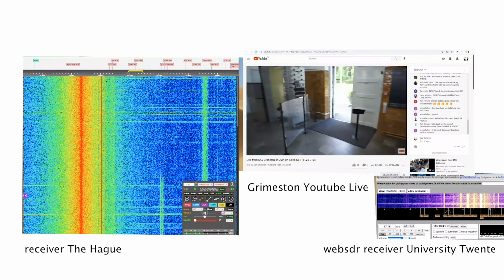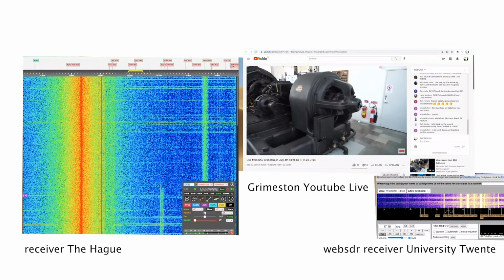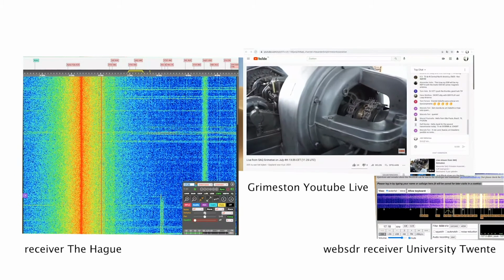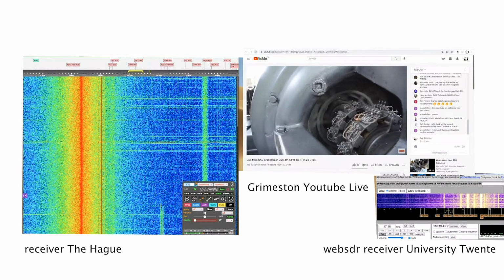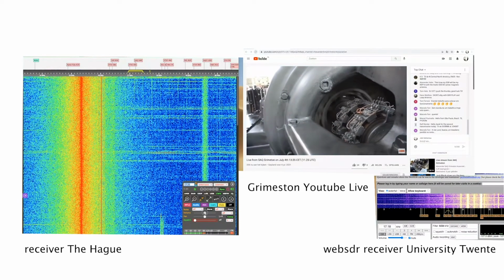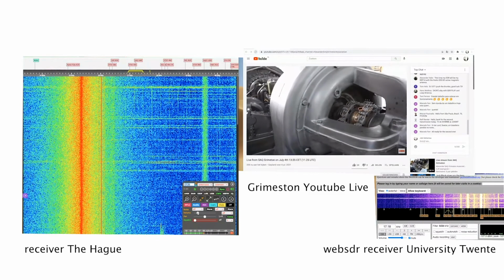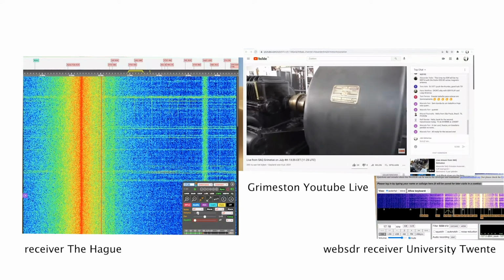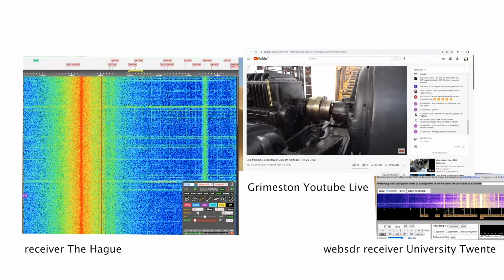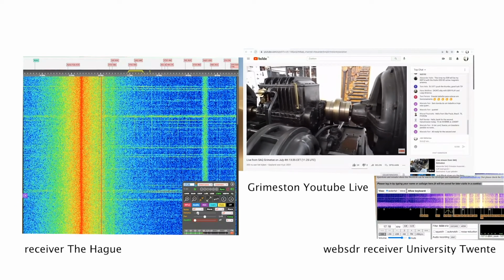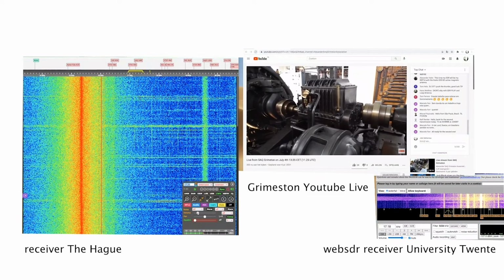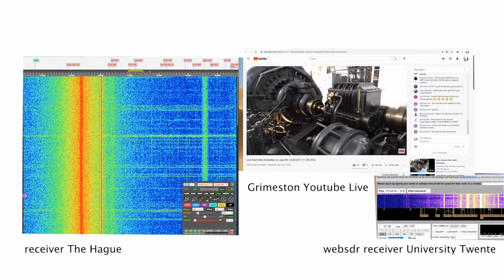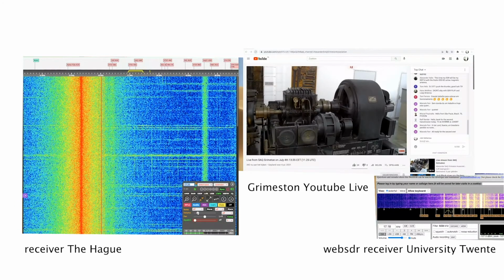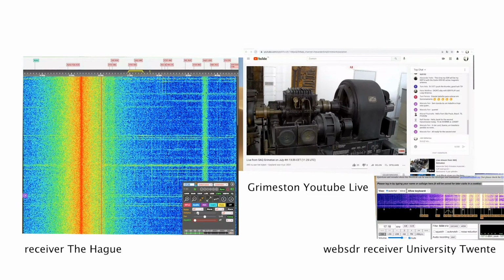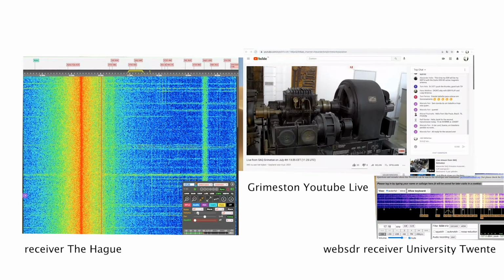Now the motor is running, slowly start to rotate because we are having high masses to be started up. Only the rotor in the alternator weighs about 1,500 kilograms. The start up current in the motor is about 250 amps, which we can see on the ammeter on the top of the panel here.